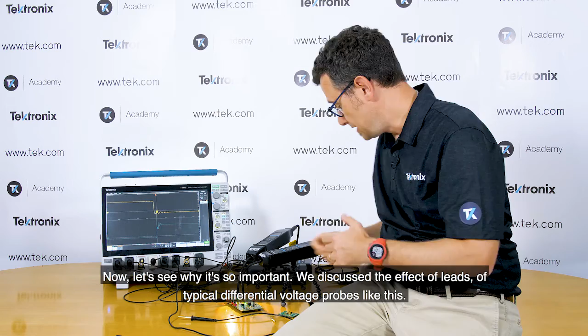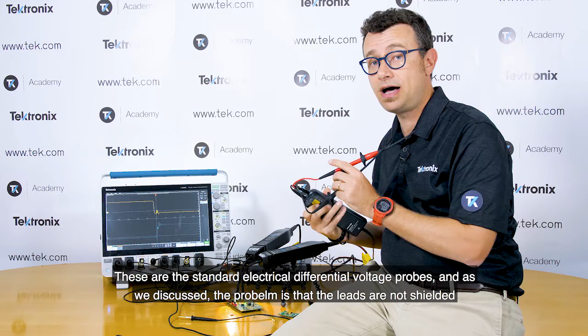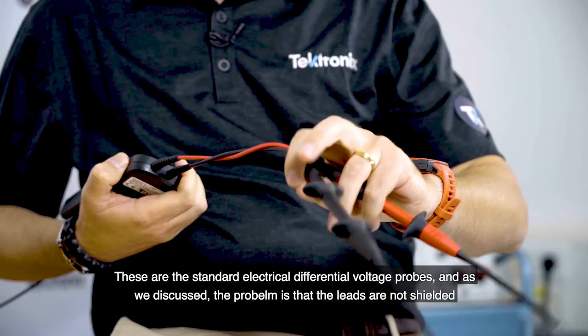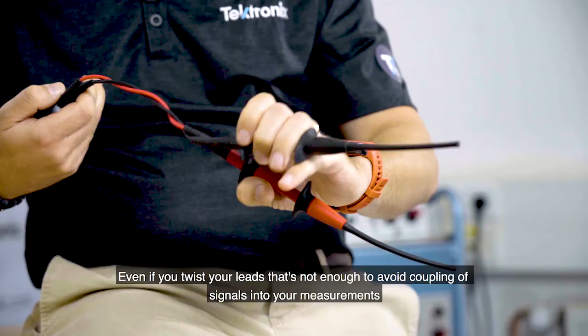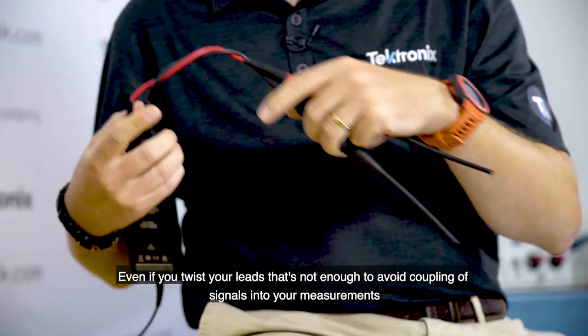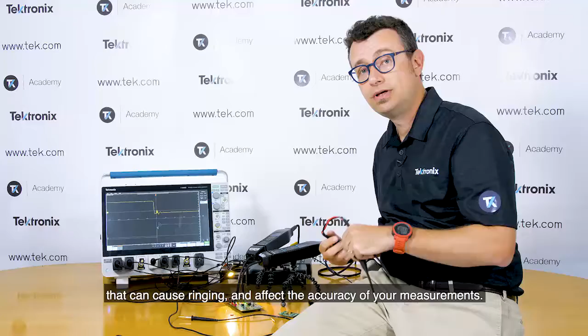We discussed the effect of the leads of typical differential voltage probes like this. These are the standard electrical differential voltage probes. And as we discussed, the problem is that the leads are not shielded and they can add parasitics to your circuit now that you are using these sensitive devices. Even if you twist your leads, that's not enough to avoid coupling of signals into your measurements, which can cause ringing and affect the accuracy of your measurement. So how do we solve the problem?